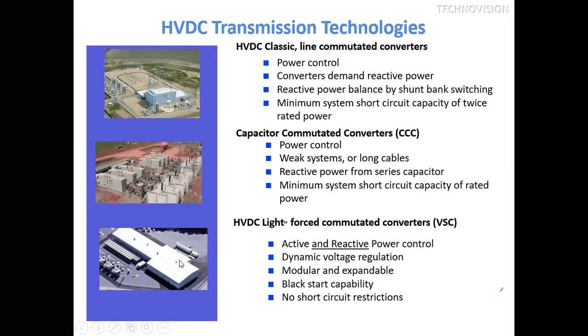Here the advantage is that active and reactive power can be controlled independently. It has dynamic control. It is modular, expandable, and has black start capability. So in case of any major grid disturbance, it acts as a charging medium for charging the other sections of the grid. That's why it is a highly advantageous technology, and Power Grid has already planned this technology and already started implementing it also.